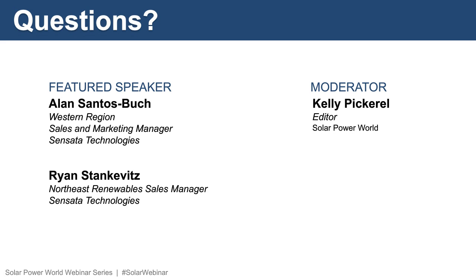That's a good question, and I am not a signage expert, but my research shows that NEC 706.11 has Part A and a Part B. Part A is for grid-connected or interconnected homes. Part B is for standalone or off-grid homes. And basically it's saying that a plaque or directory denoting all power sources shall be installed at each service entrance equipment location on a grid-connected home.